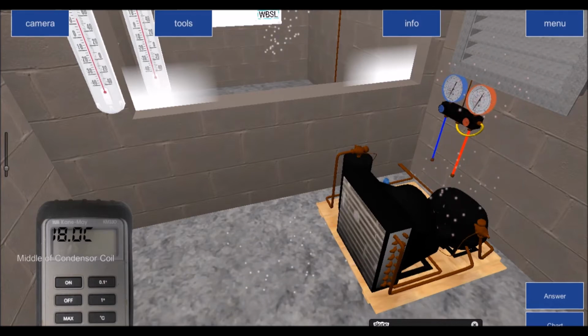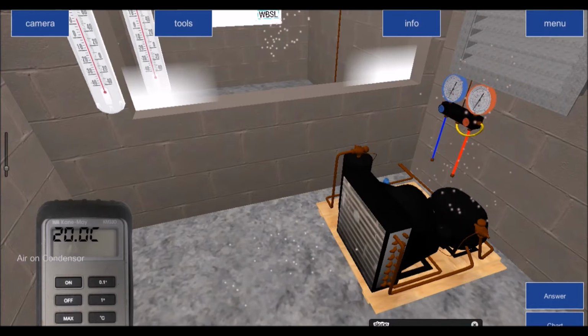So this is why it's important to know that when we come to a system and we're going through the checks and balances, and we're determining, is the temperature that I'm getting at this component the normal temperature that I would expect, you need to benchmark it against the ambient conditions. In the case of the two heat exchangers, you need to benchmark it against the ambient conditions that those actual heat exchangers are located in. So in this particular case, this heat exchanger, which is a condenser, is located in an air-on of 20 degrees. So the air coming onto the condenser is 20 degrees Celsius.